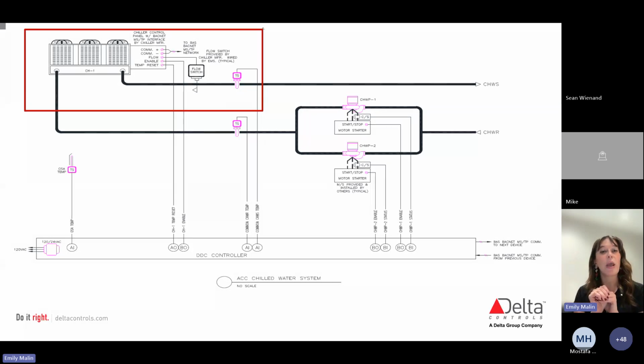So if you need to zoom in, you can. But what we're seeing up top there in a real diagram and a schematic like this one is the chiller itself, right? So you can see on there that the drawing indicates that this is going to come with a panel that's going to be interfaced via BACnet MSTP. And again, we talked about those protocols in 102. So we need to make sure that whatever network we're communicating on in our whole system is also going to be able to talk to our packaged component, which is going to be that chiller. So we know that that's going to interface via our protocol of BACnet MSTP.